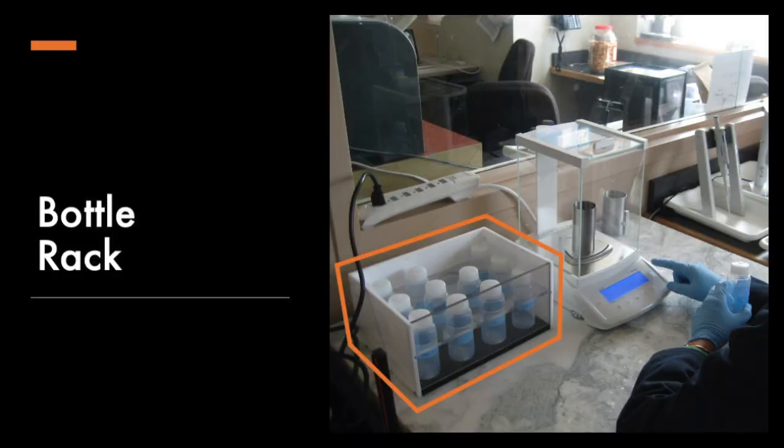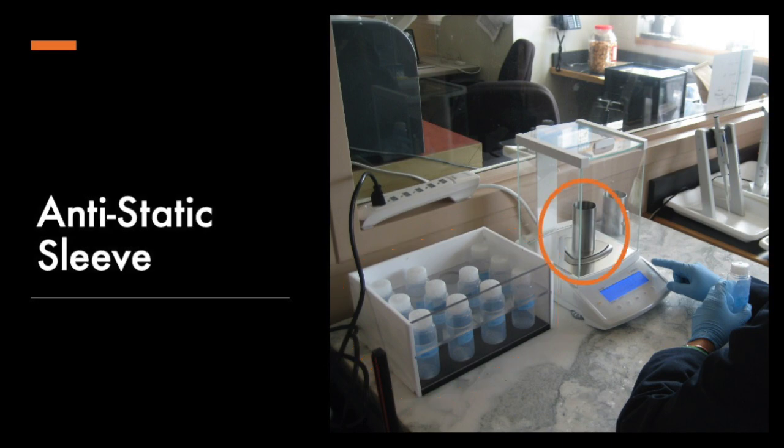Here's that bottle rack. You can see each of the Teflon bottles held within acrylic and with a Teflon surround on there. The other purpose of this rack that you'll see in one of the next videos is that it keeps the bottles warm as they're sitting on a hot plate, which increases the speed and the uniformity of the digestion with the HF. We have a little anti-static shield on that balance. It's a sleeve, and it's just made of metal, and it bleeds static off the Teflon bottles. In the middle of winter, in labs that get really dry, there can be an awful lot of static.